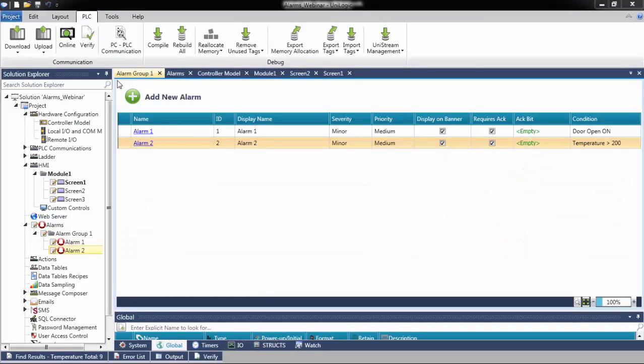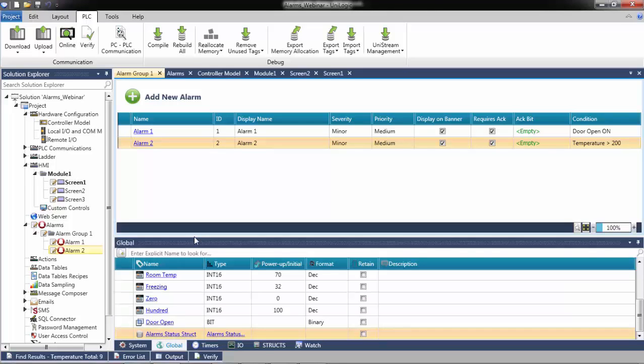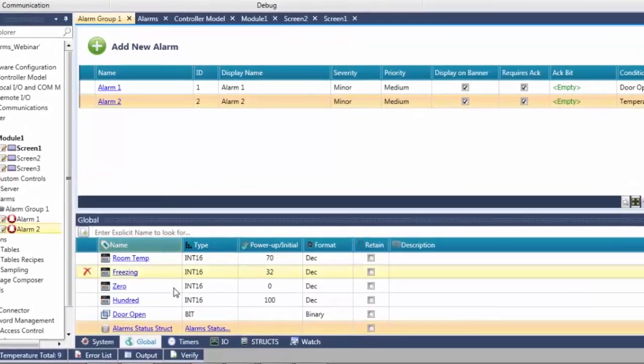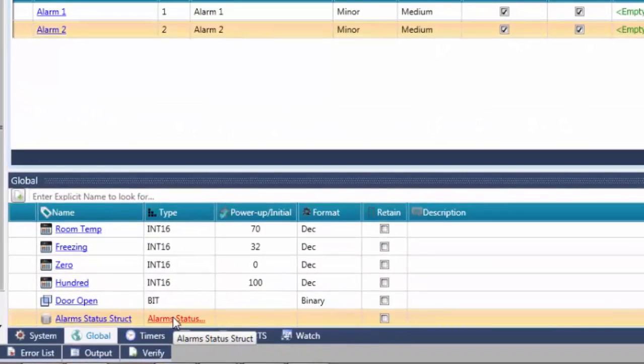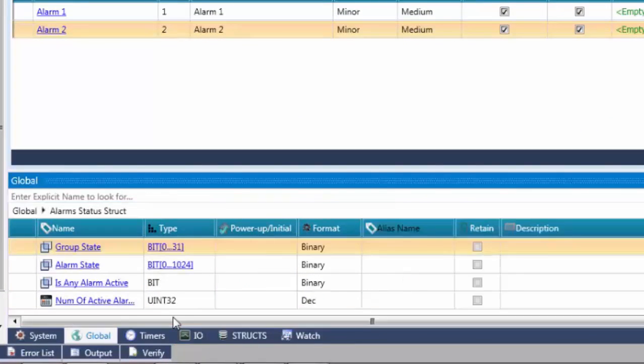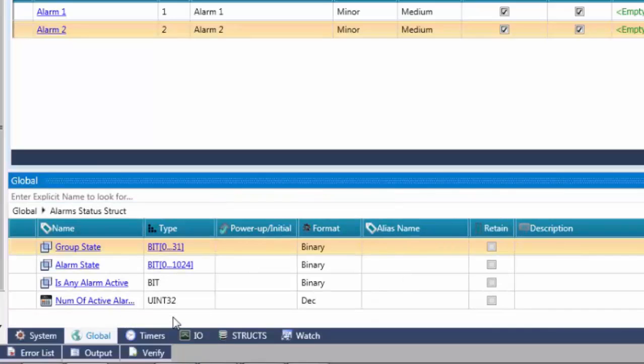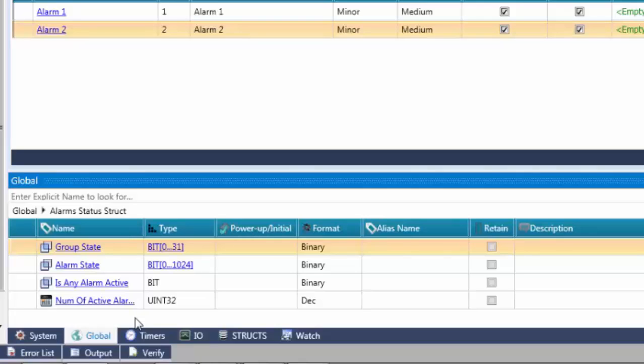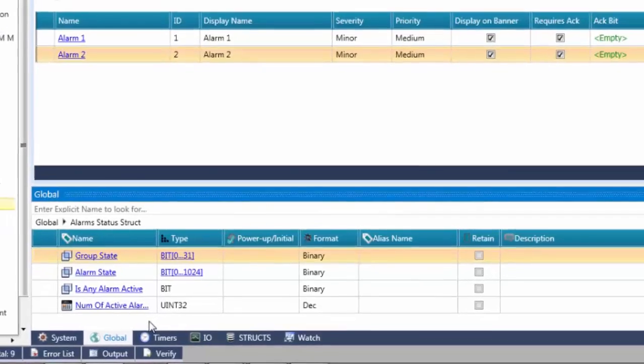The temperature alarm is now complete. When an alarm tool is added to a project, Unilogic creates an alarm status struct to enable easier handling. Those struct members are group state for groups of alarms, alarm state for single alarms, an is any alarm active bit, and a number of active alarms integer. These members give the user the ability to use the state and quantity of the alarms in their ladder logic.